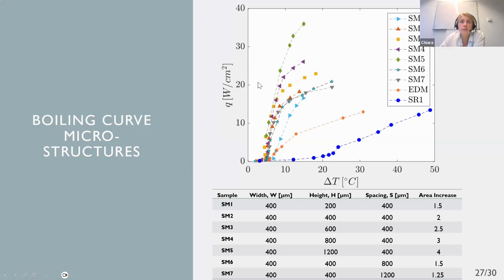Yeah, so the temperatures are measured with the thermocouples, and we calibrated them. We didn't use the manufacturer calibration, but we calibrated them in situ in a water bath. So the uncertainty on the temperatures goes down to 0.1 degrees.